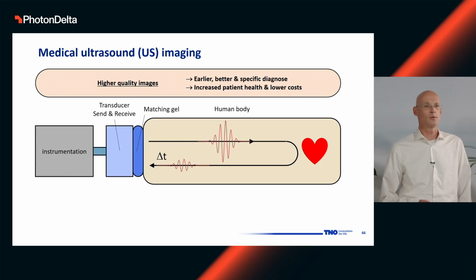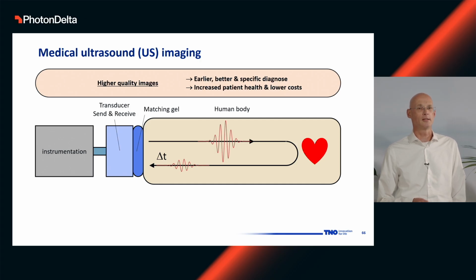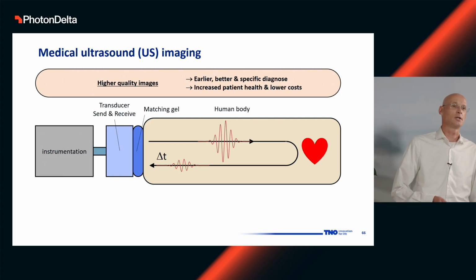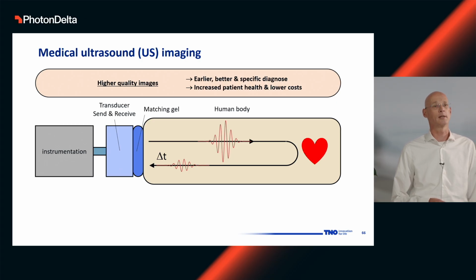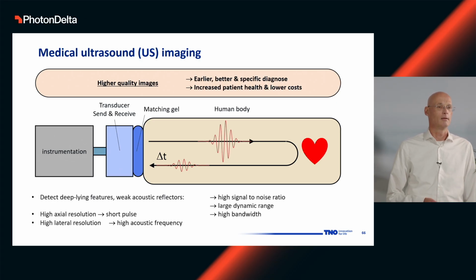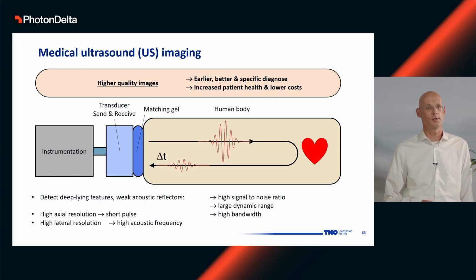Now, the way ultrasound works, in a disrespectful way of saying it, for photonics people, it's like an acoustic LiDAR. It's a bit disrespectful, but the way it works is essentially you have a transducer which emits a short sound pulse, typically in the megahertz range, into the human body. And this sound pulse reflects from organs, for example, like the heart. And then the reflection arrives back to the transducer, which does both emit and receive. And the key features here are that deep-lying features have only a weak acoustic reflection. So, of course, the deeper the organ, the weaker the reflection. So you would like to have a very low detection limit, so high signal-to-noise ratio. But there are also stronger reflections, so you also need a large dynamic range.